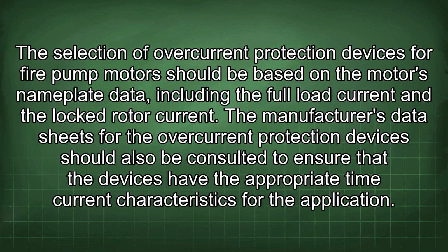The selection of overcurrent protection devices for fire pump motors should be based on the motor's nameplate data, including the full load current and the locked rotor current. The manufacturer's data sheets for the overcurrent protection devices should also be consulted to ensure that the devices have the appropriate time current characteristics for the application.